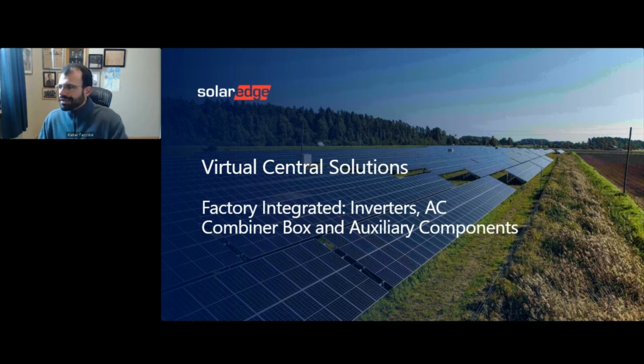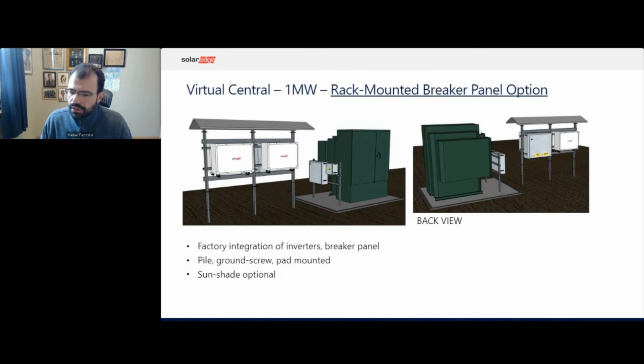We have created 2 standard designs, a 1 megawatt and a 2.5 megawatts. While other sizes are allowed, these standard designs sizes will have shorter lead time due to shorter engineering cycles. So the first design is a 1 megawatt AC, and the design includes an inverter rack with 3 inverters, AC breaker panel, and other auxiliary components. So very simple, it can be wired in the factory and sent to the field so that you can just make the connection between the transformer and the AC breaker panel.